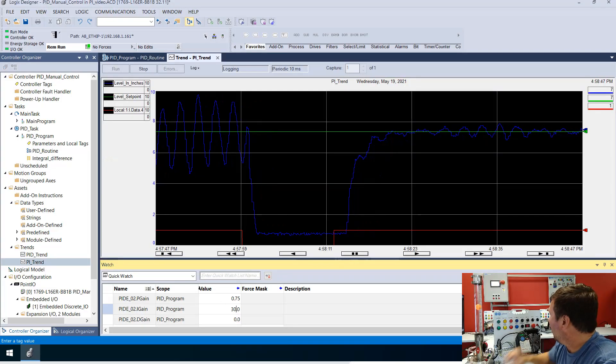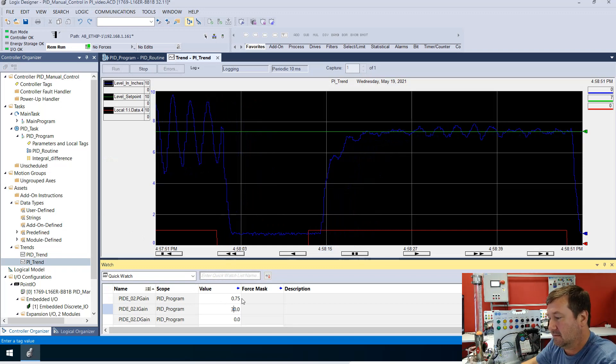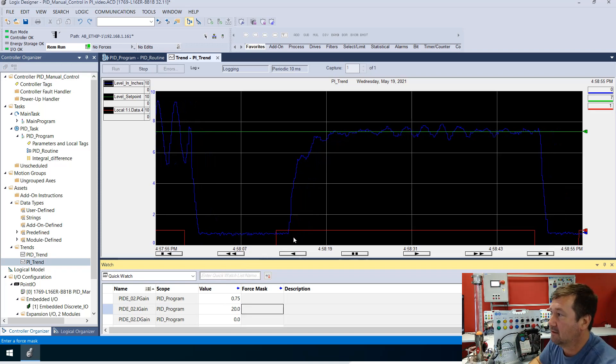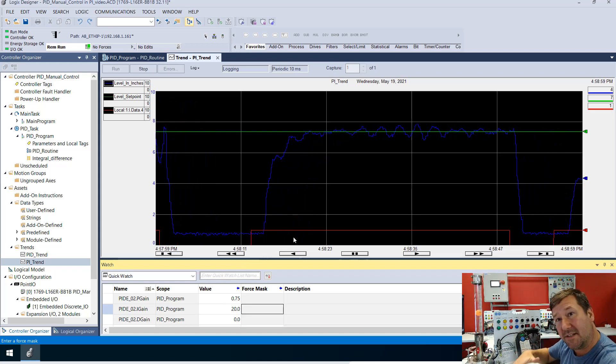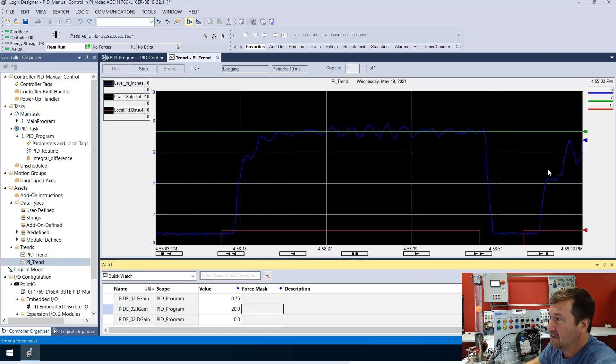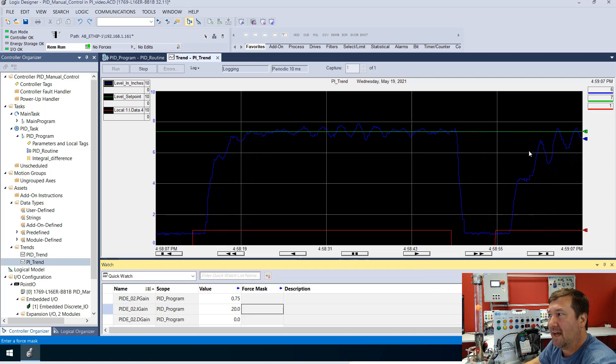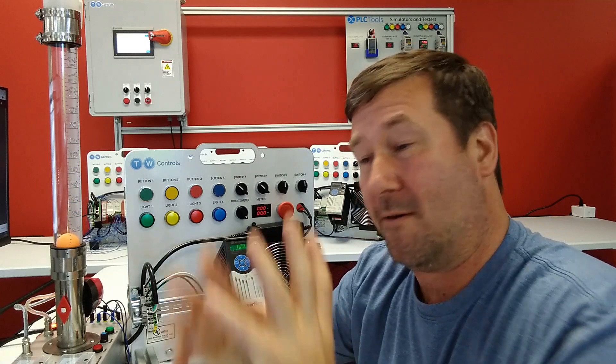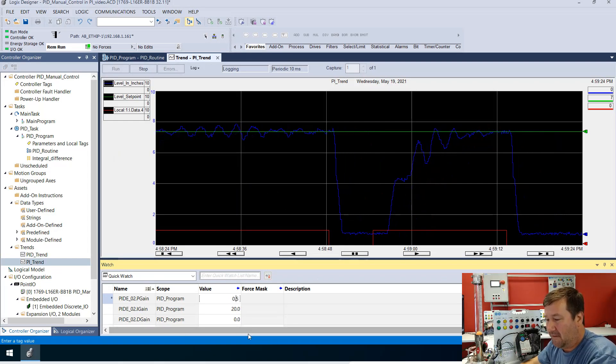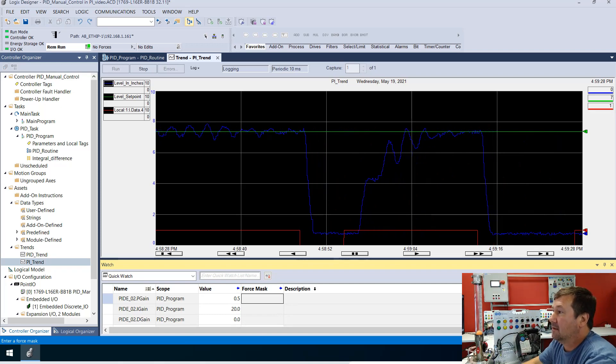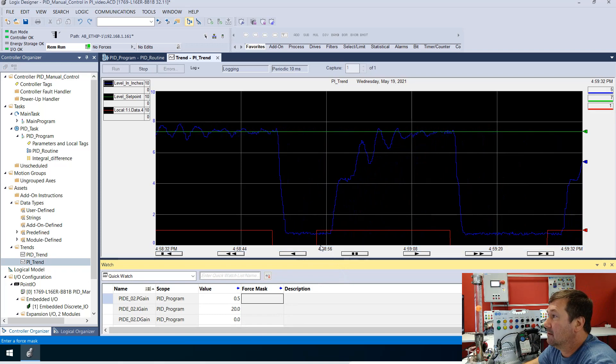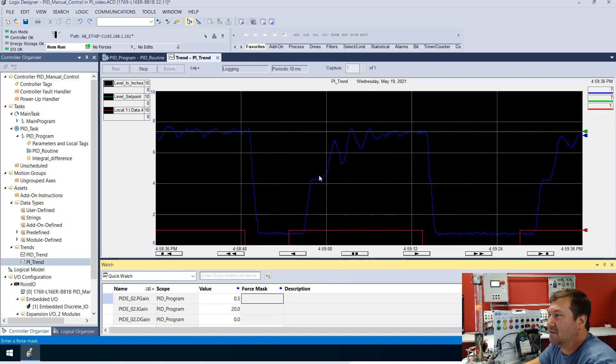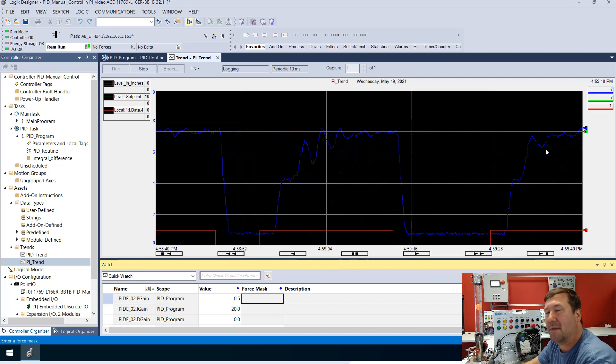Now let's say we wanted to change our I though. Let's say that maybe it's too aggressive. Let's take our I to 20. And we'll try it again. So now since our I value or our integral value is lower, it's going to take longer to adjust over time. And also you can see that proportional, we're getting a lot more back and forth. Our proportional now is too high for this particular integral. So there is no perfect proportional or perfect integral. As you change one, the other will need changed. So we see it's too much. We're going to try 0.5 now. And we did have a little sag, same as that sag there. But okay, overall, that's better.